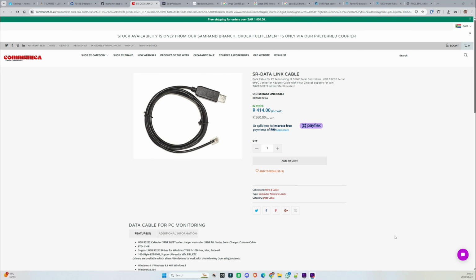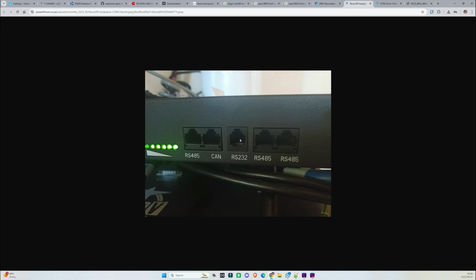The fifth thing you might need is a data link cable. You'll only need this if the RS485 communications isn't working from your battery. You'd connect using this RJ12 connector into the RS232 port, then use software called PBMS tools, which I'll include links for. Download that, then go into the management software and enable comms over the RS485.